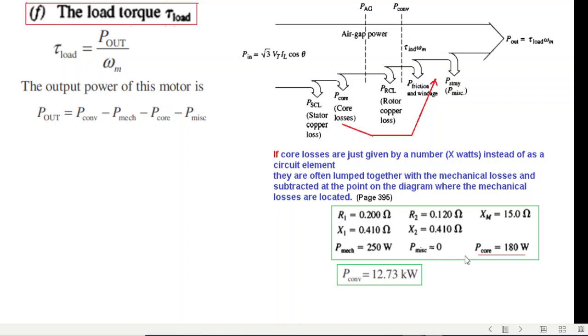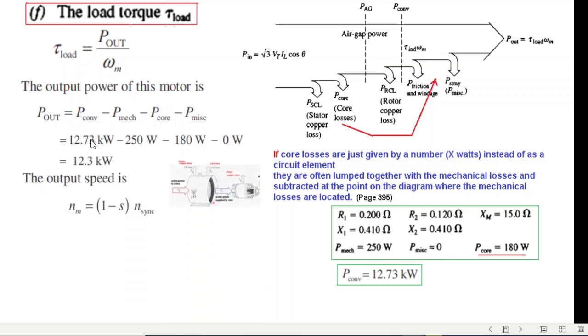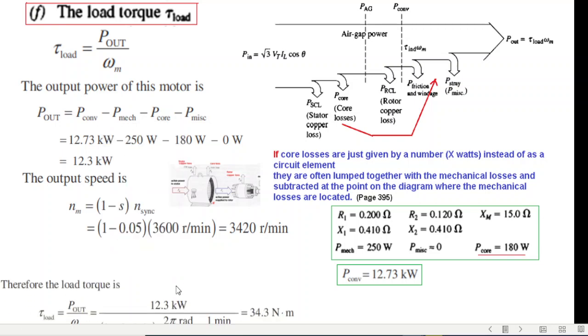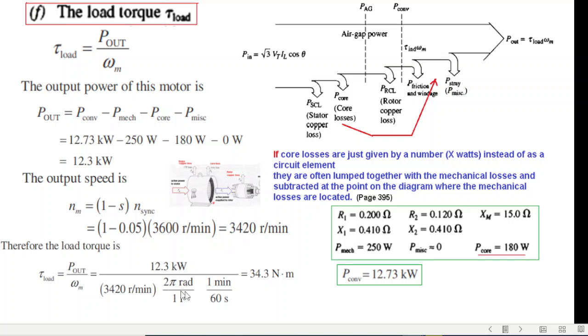We know the values of all these losses, so plugging in P_converted, P_mechanical, P_core, etc., the output power P_out is 12.3 kilowatts. For omega_m, the mechanical speed is less than synchronous speed by a factor of (1 minus s). We know slip and synchronous speed, so we calculate the mechanical speed and then convert to omega_m: mechanical RPM divided by 60 times 2π radians. The load torque comes out to 34.3 Newton-meters.